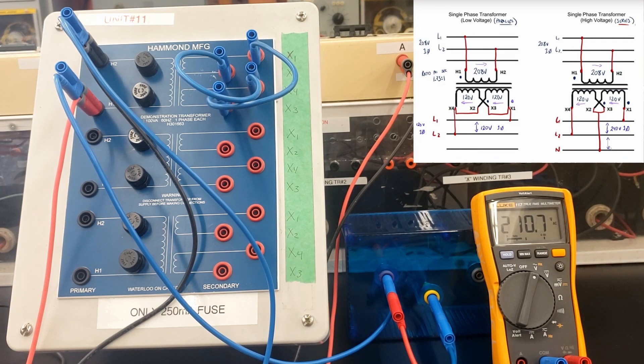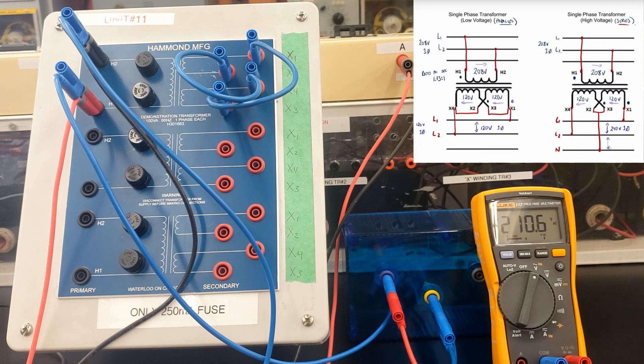I'm going to take the connections off the secondary there. We clearly saw that there was equal voltages on our secondary, 125 volts each. And that's coming from our primary. And the primary voltage is 208. Today it's 210. It really depends on whether the big compressor at the end of the hall is on or not.